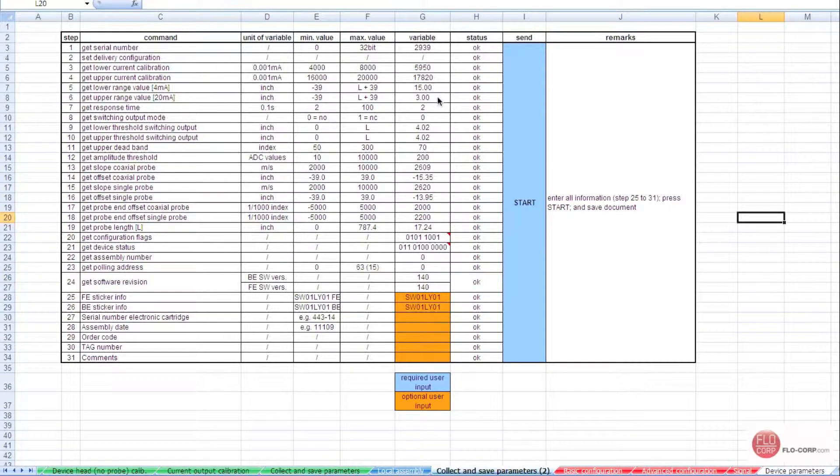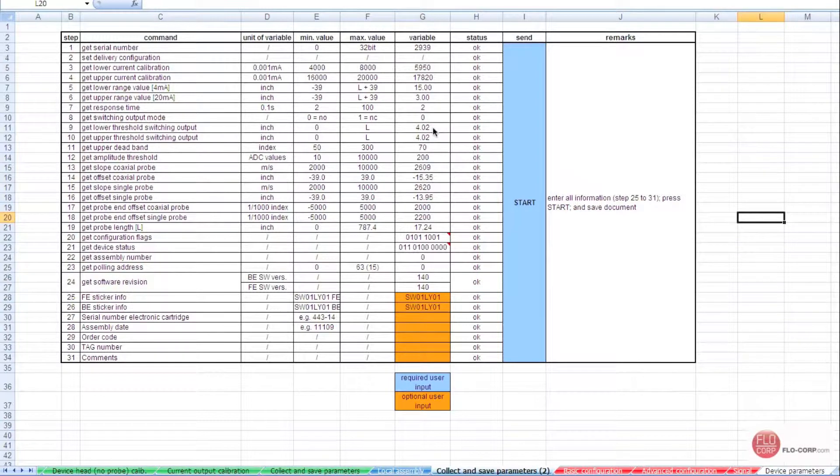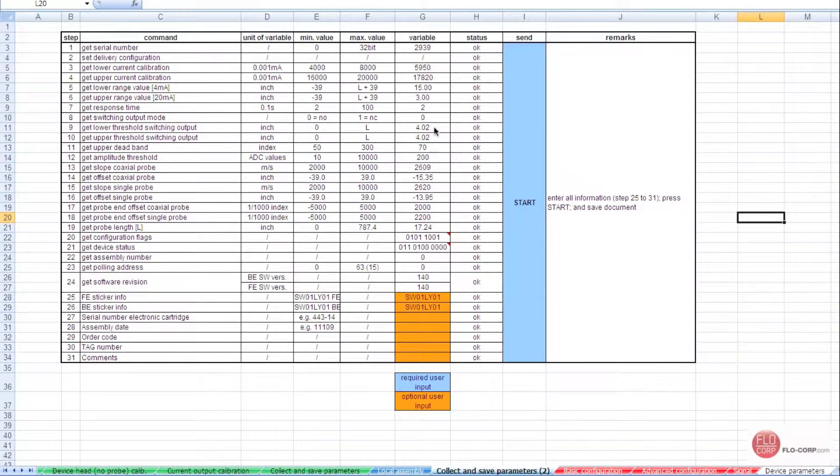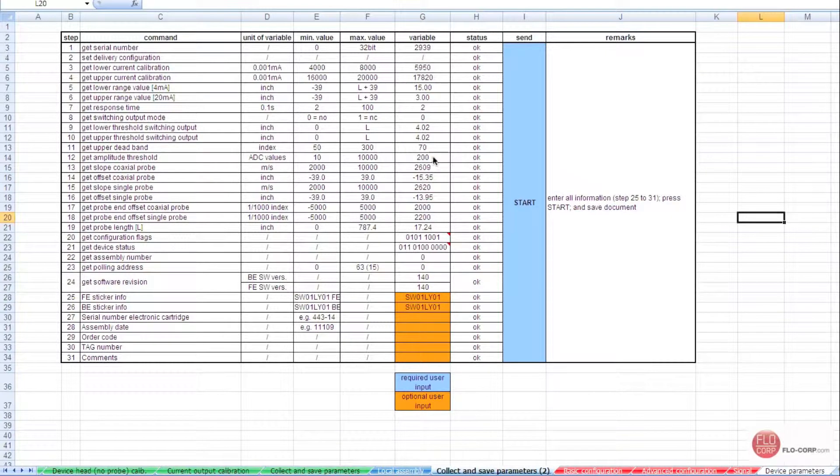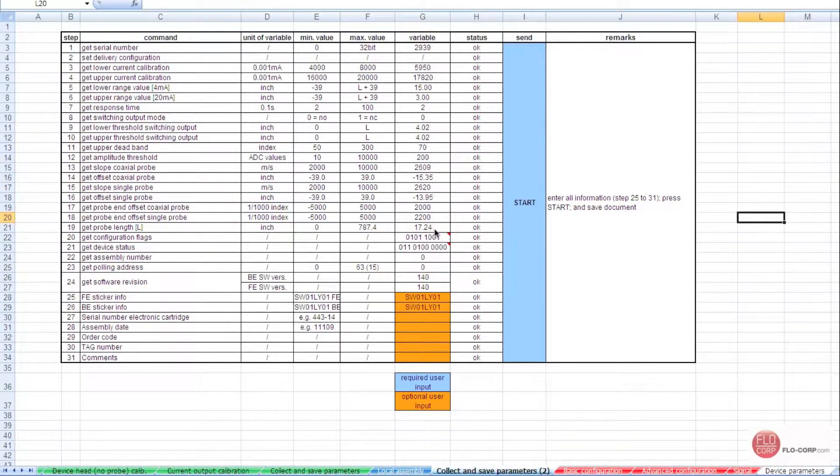Also, we can verify our upper and lower switching points, which is at 4.02 inches. We can verify our amplitude threshold, which is set for 200. We can verify our probe length, which is 17 inches.